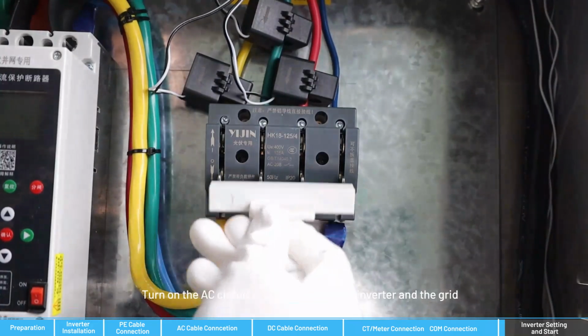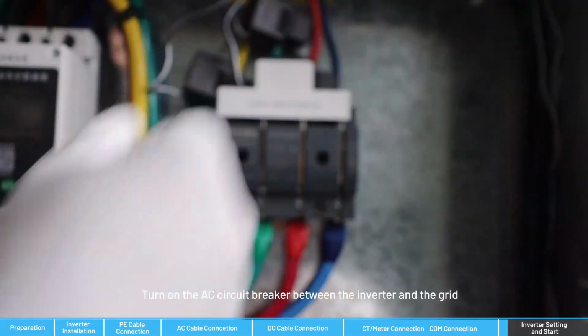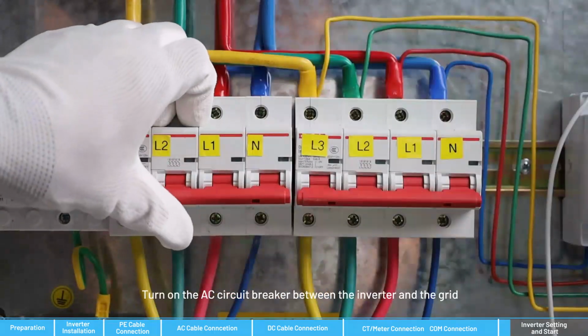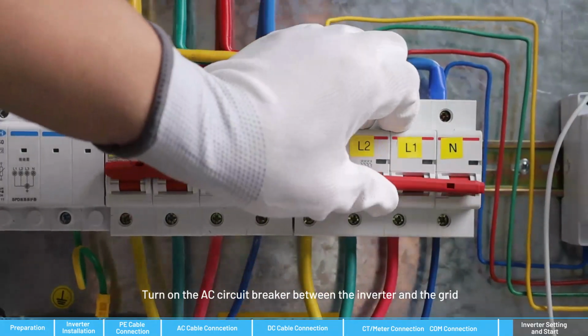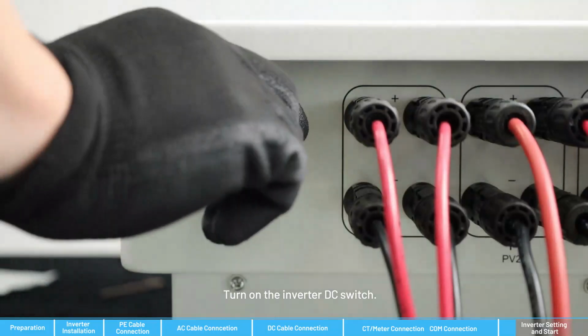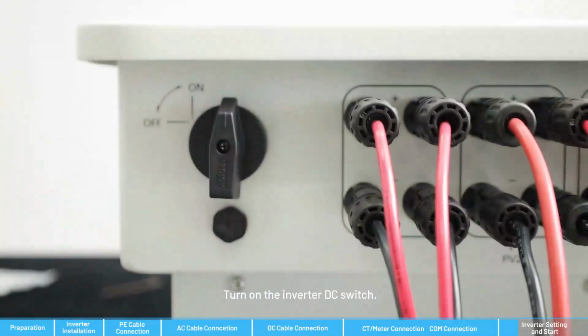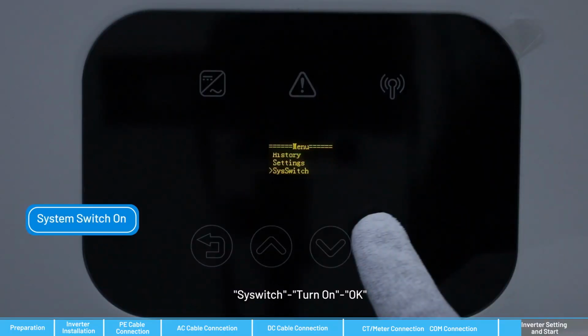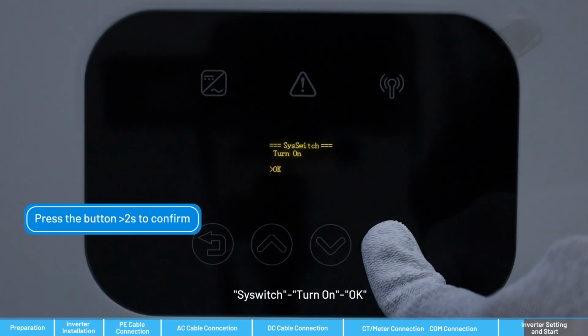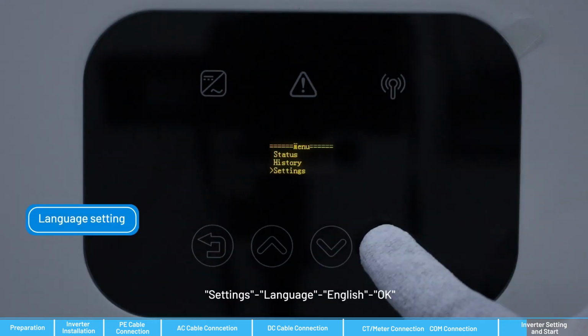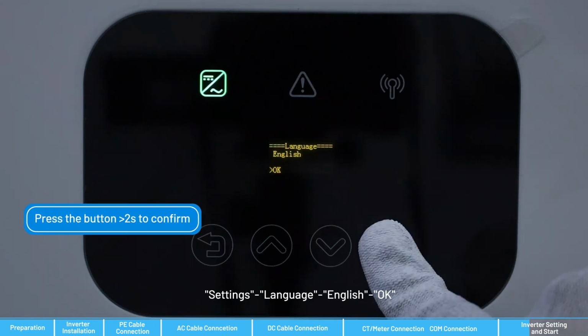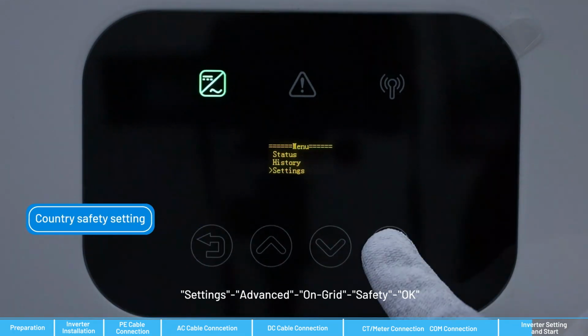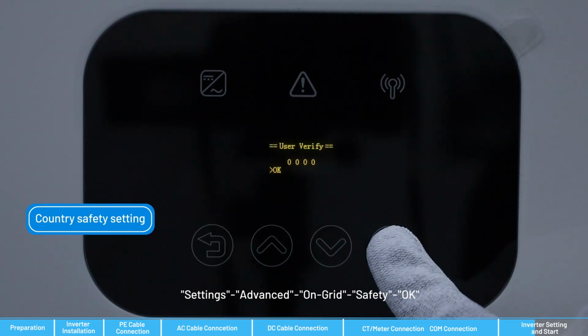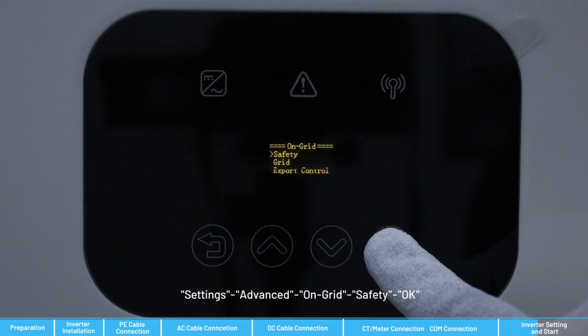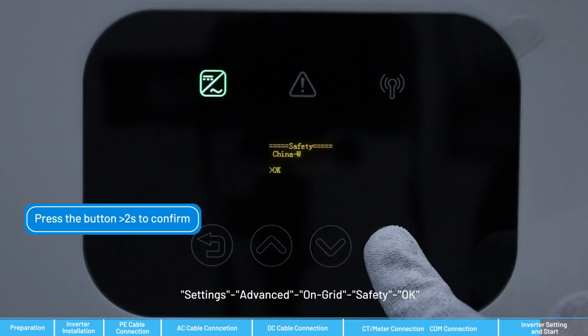Turn on the AC circuit breaker between the inverter and the grid. Turn on the inverter DC switch. Sys switch. Turn on. OK. Settings. Language. English. OK. Settings. Advanced. On grid. Safety. OK.